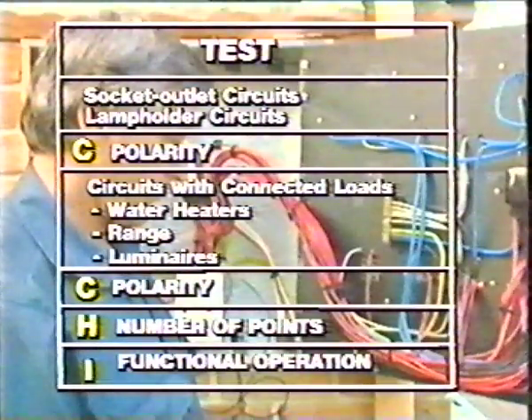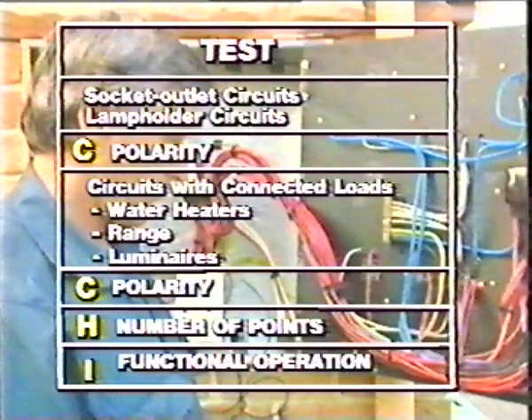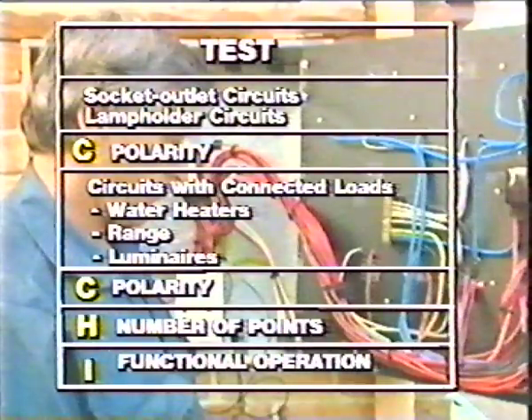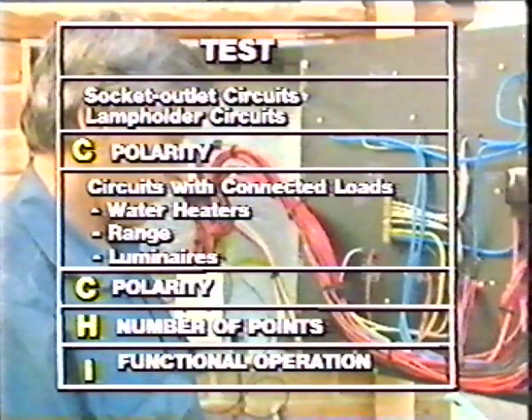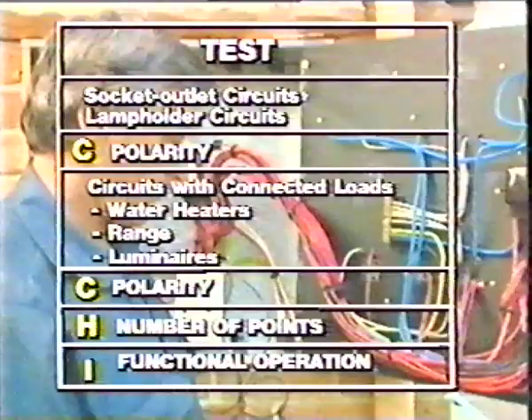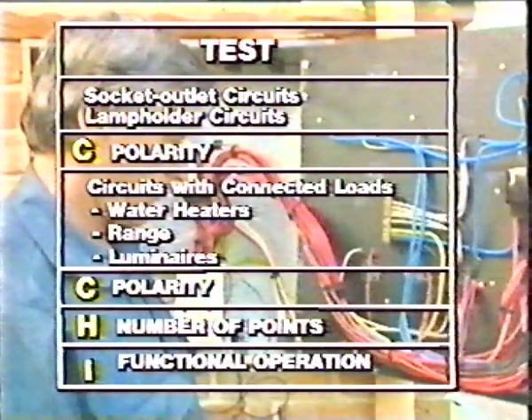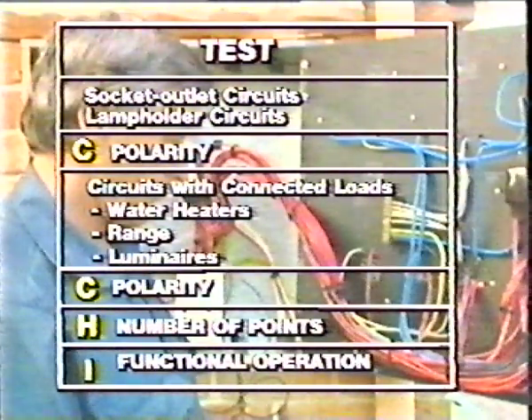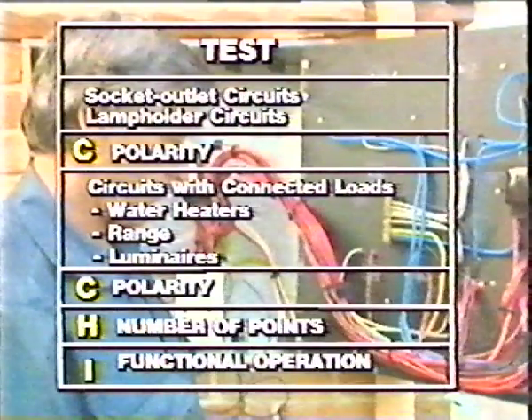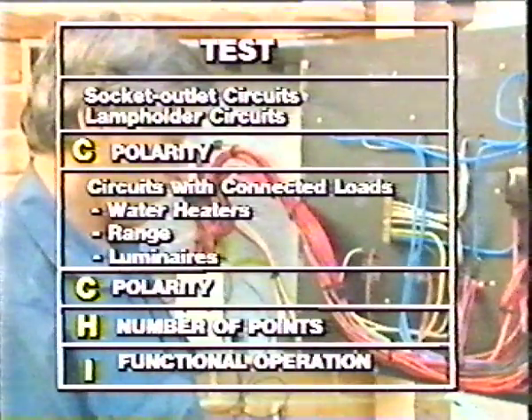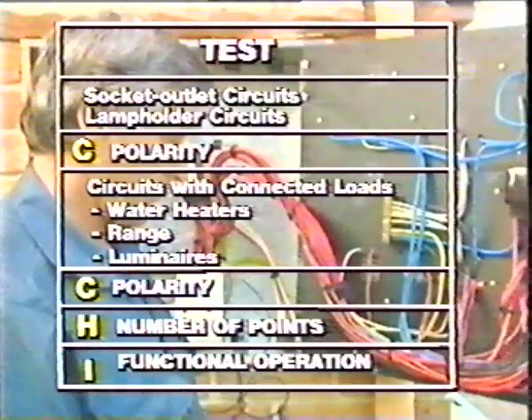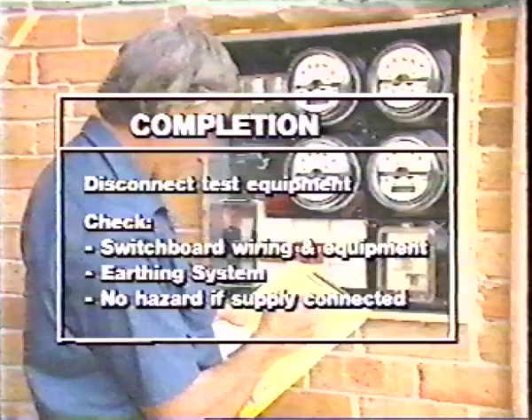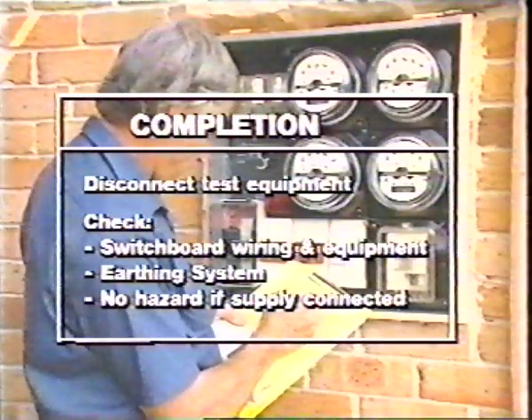A comprehensive functional operation test cannot be carried out if supply is not available. But after completing the tests which have been outlined, the installation can normally be safely connected to the supply. If supply is available, test D, neutral earth transposition, and test C, polarity, can be tested using test lamps as demonstrated in part 1. After completing all tests, disconnect the test equipment.